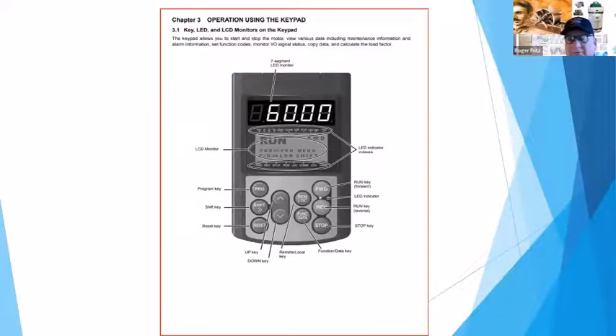Whether you want people to be able to access this keypad, you can take functionality to shut it down. So it becomes more of a dummy site, monitor data only. So you can go up and down the arrow, and you can watch your amperage. A lot of them have an LCD point, but as you scroll up and down, you're just scrolling between readings. It may read the voltage, it may read the amperage, it may read the pressure setting on a pressure transducer. It may read the analog input reading off of a sensor.